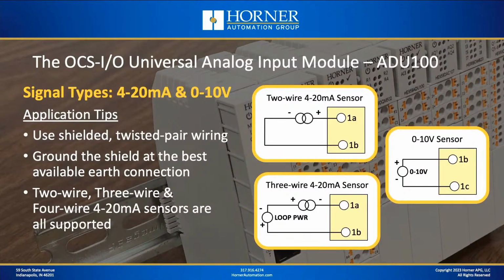Now let's talk about some application tips, and we're going to start with wiring. We mentioned earlier that there are 4 terminals on each channel, A, B, C, and a 0-volt terminal. Depending on the sensor that's connected, you're going to find either the A, the B, or the C, or some combination of those will be used. So let's start with the 4 to 20 milliamp and the 0 to 10 volt wiring. You'll see that the A and the B are used for current signals, and the B and the C are used for voltage signals.